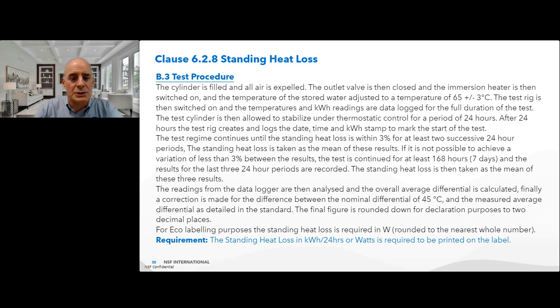If it's not possible to achieve a variation of less than 3% between the results, the test is continued for at least 168 hours, so a further 7 days, and the results of the last 3 24-hour periods are recorded. The standing heat loss is then taken as the mean of these 3 results. The readings from the data logger are then analysed and the overall average differential is calculated. Finally, a correction is made for the difference between the nominal differential of 45 degrees and the measured average differential as detailed in the standard.